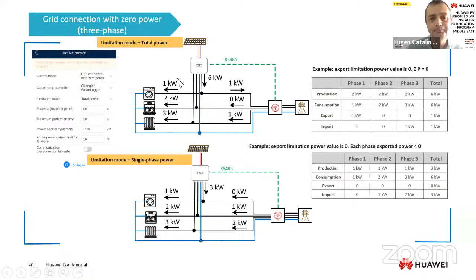In this situation, the inverter will export the same, 6 kilowatts. We split it for each phase, 2 kilowatts. In single phase power, the inverter will take as reference the lowest phase. We'll export 1 kilowatt per each phase. In case you have a very unbalanced situation and do not want to export some energy, you will choose single phase in order to adapt the inverter to the lowest phase that you have.